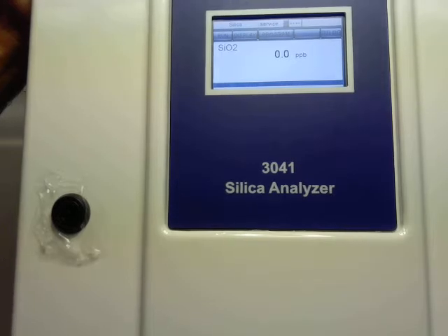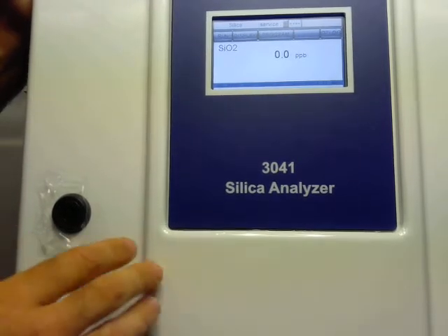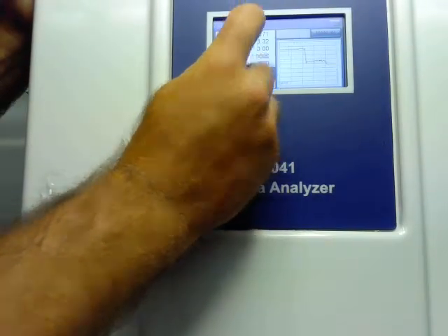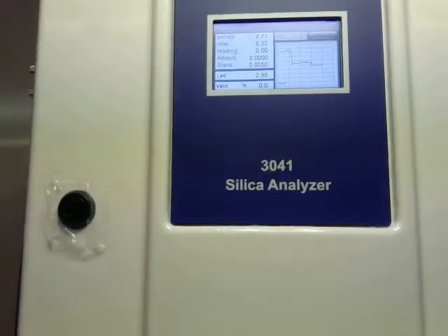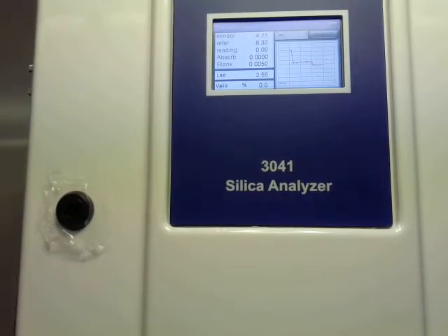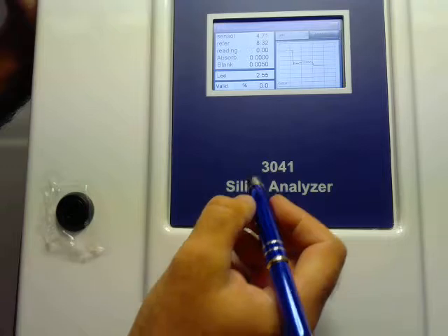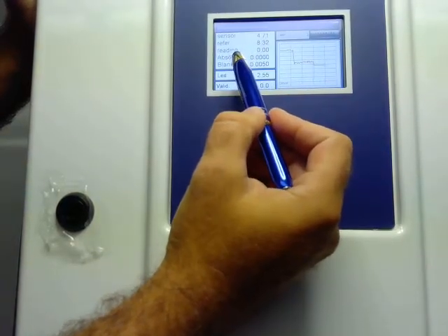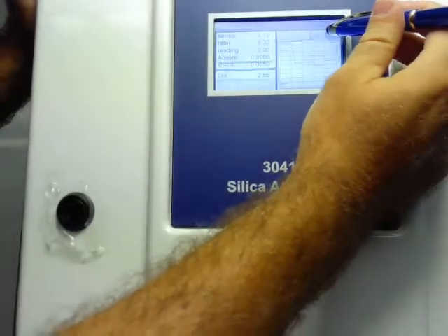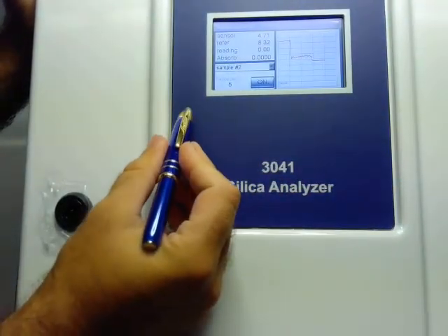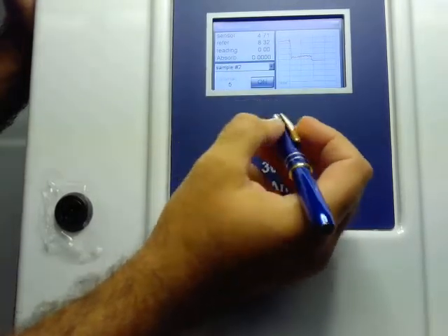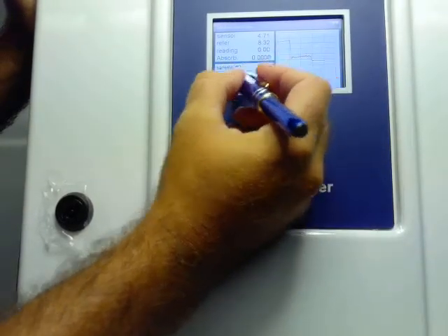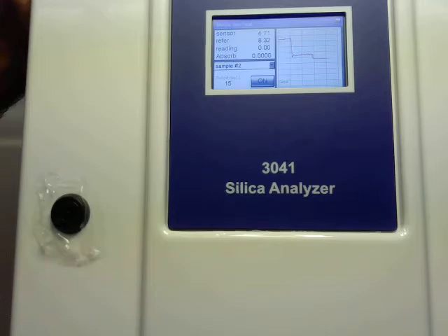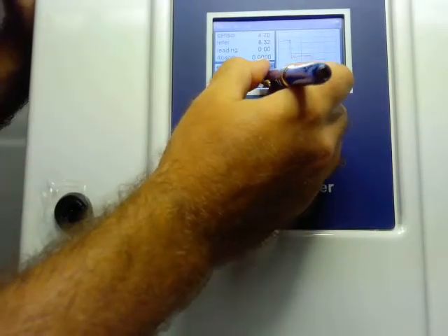So once we've got our reagents installed and we've updated the counter, we'll want to prime the lines. So we'll hit this display menu, and this will bring up our screen that has all these reference readings and sensor values. We'll come over to our manual screen, which shows a drop-down menu of all the commands that we can run. The first thing I'm going to do here is a sample 2 for 15 seconds, which is just going to draw in calibration standard and fill up our flow cell with a little bit of standard. And once I hit that, you can probably hear the pumps starting to turn.